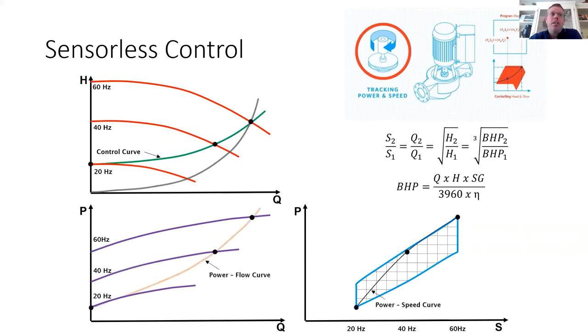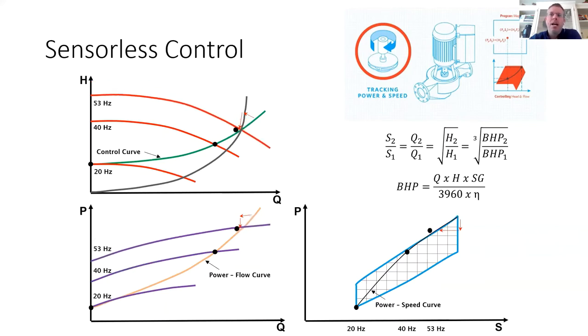And so as valves start to close out in the system, your flow is going to drop and your head is going to increase, but it's going to be in a square root relationship. So the resulting power consumption at that given speed is actually going to drop. So that's going to take you off the power-speed control curve, and in order to get back onto the control curve, the pump controller will slow down the speed of the pump until the appropriate power consumption is reached via their map.